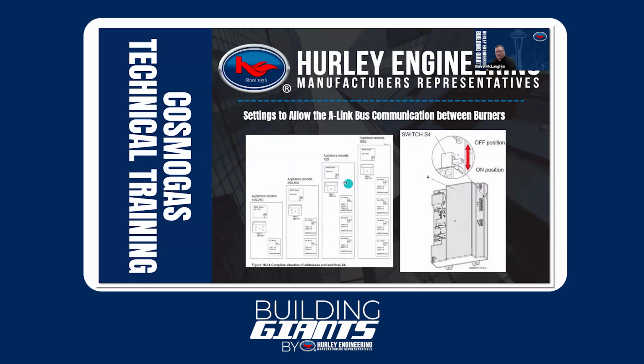Whenever you do that, there are certain things that you have to change. You can see here, if I'm running 2 heat exchangers, here's my dip switch on the controller, and you can see over here the dip switch location and what position it indicates. Down is on, up is off. So if I had 2 heat exchangers, my master would need to go to parameter 3001, set to 2, go to 2003, set to 0, and make sure my dip switch is off. Same thing on this bottom board, my dip switch should be down. Here's what my parameters are set to. But basically for any configuration here, if I have to unplug and replug and change one of these boards, they tell you exactly what you need in order for that thing to communicate and operate correctly.